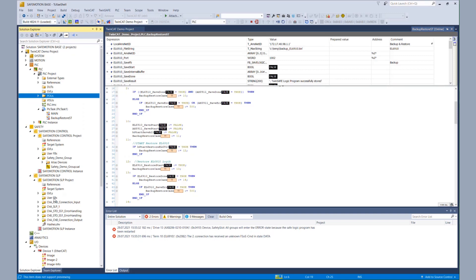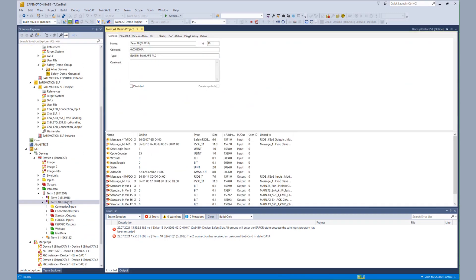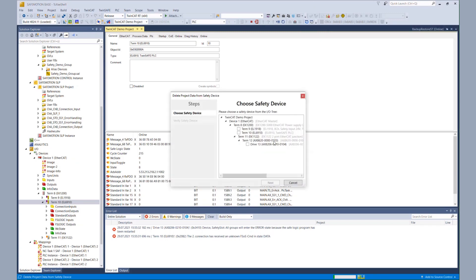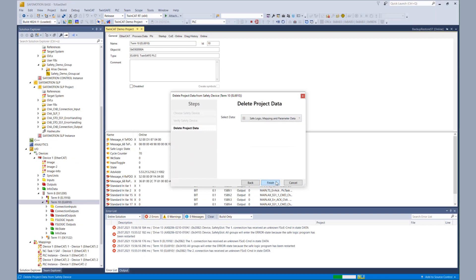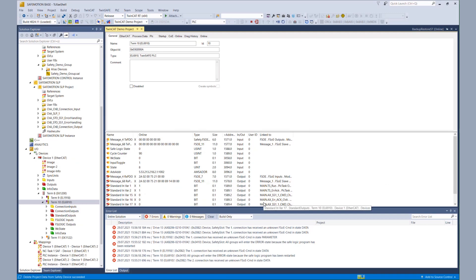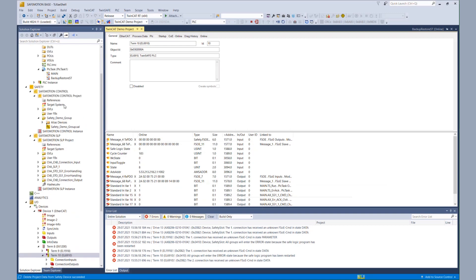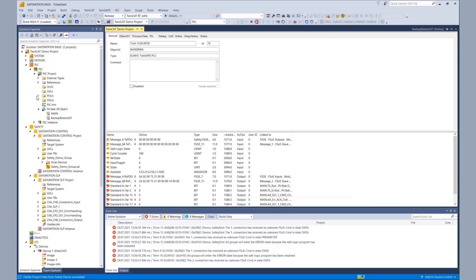Now we want to test our restore mode. We go to the process image again to check that both projects are still running, and now we are deleting the first project. In the first case, we are deleting the EL6910 project. We put in our username and password and start the deletion process. We delete everything from the terminal, and via the process image, we see that the EL6910 is now talking no more with the yellow components.